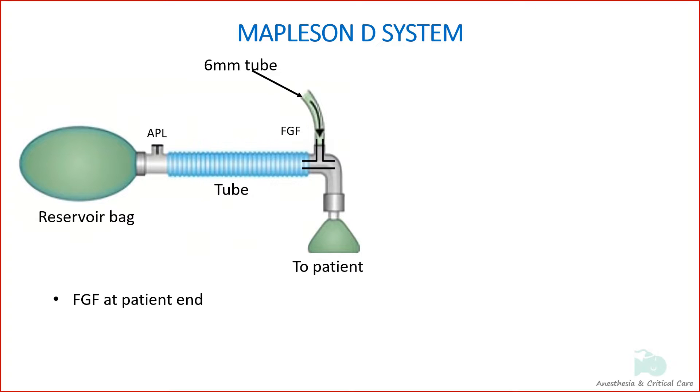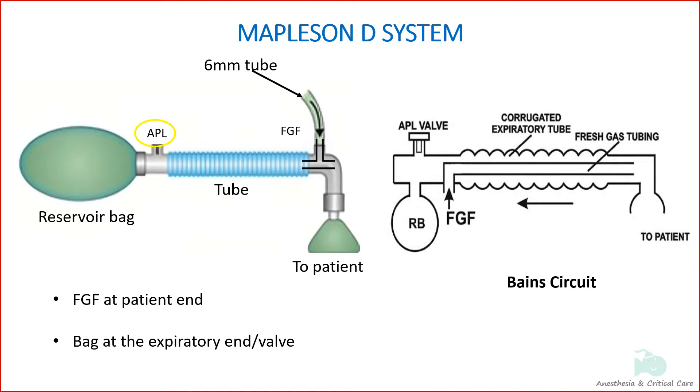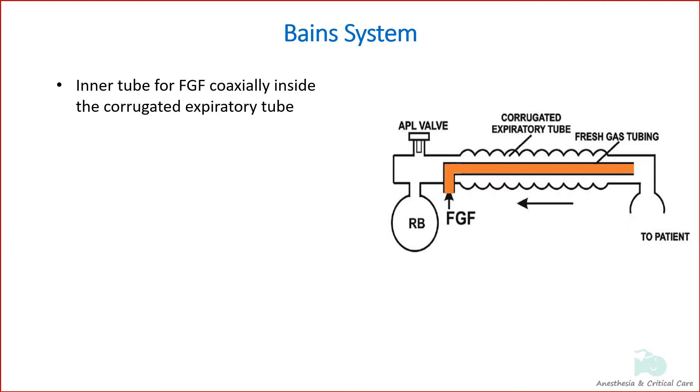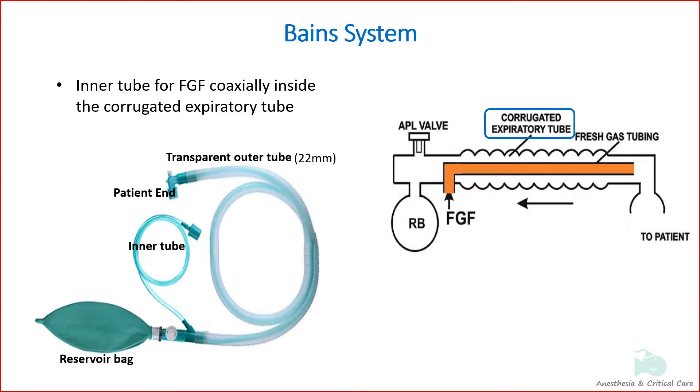The expiratory valve is positioned near the bag. The modified version of Mapleson D, called Bain's circuit, is the one used clinically. Bain's system was introduced by Bain and Spoerel in 1972. In this circuit the fresh gas supply tube runs coaxially inside the corrugated tubing. The diameter of the outer tubing is 22mm, the inner tube is 7mm, and the length of the circuit is 1.8 metres.